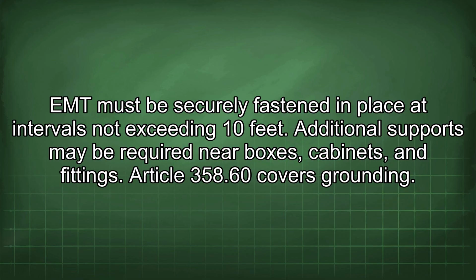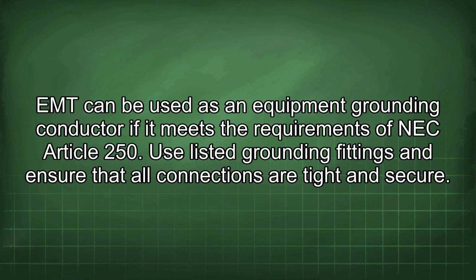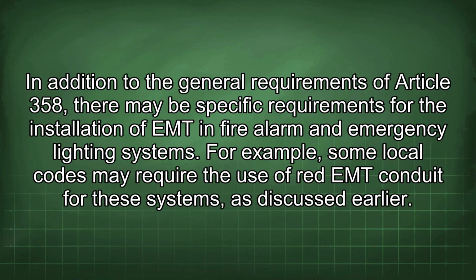Article 358.60 covers grounding. EMT can be used as an equipment grounding conductor if it meets the requirements of NEC Article 250. Use listed grounding fittings and ensure that all connections are tight and secure. In addition to the general requirements of Article 358, there may be specific requirements for the installation of EMT in fire alarm and emergency lighting systems. For example, some local codes may require the use of red EMT conduit for these systems, as discussed earlier.